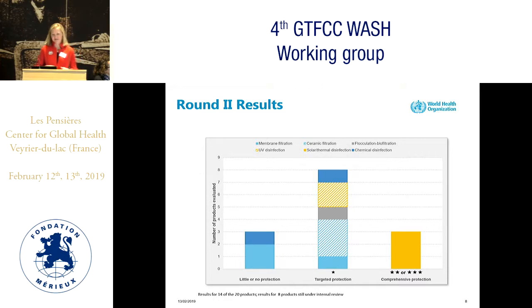So this kind of approach, drop a tablet in and pray that you'll reach the right residual, I guess in a lot of cases it may work, but what we found is that chlorine demand is very variable. It depends on lots of variables even beyond the organic matter you have: salt, temperature, pH, and that really means that you need to have a very specific approach.